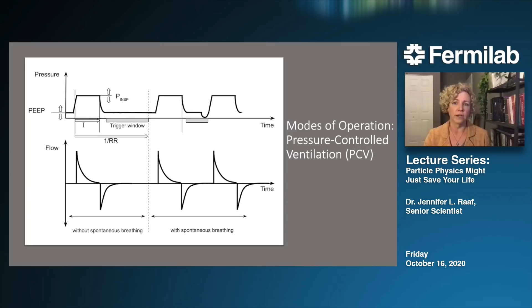The other mode that the MVM provides is called pressure support ventilation. And in this one, the ventilator takes over part of the work of breathing. The patient maintains the control of the respiratory rate. So in this mode, pressure support is triggered when the patient initiates a breath, and that's done by that same pressure drop that we saw on the last page, the little dip at the beginning. And then the pressure is provided up to the target P-insp pressure.